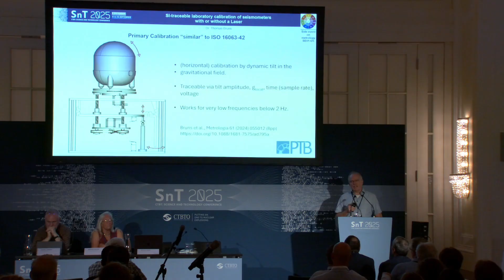For low frequency, we found that this tilt effect of the airborne shake table is really a problem, where you get dynamically changing gravitational influences. It gives you some deviation in the low frequency range, and you are better off if you use a tilt table for low frequencies. We developed a specific method at PTB, because the tilt table gives you a very defined angular tilt, but it also introduces a trajectory where the seismometer is moving on the circumference of a circle around the tilt hinge. So we developed a method where you can compensate for both influences and then get very precise measurements at low frequencies for seismometers.